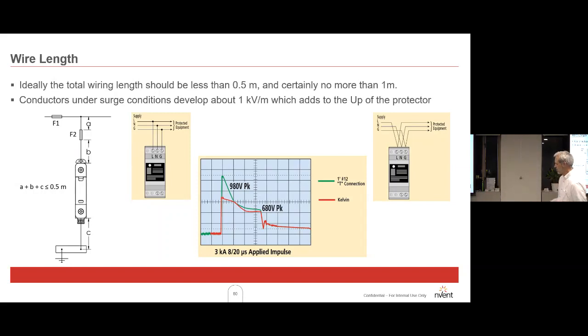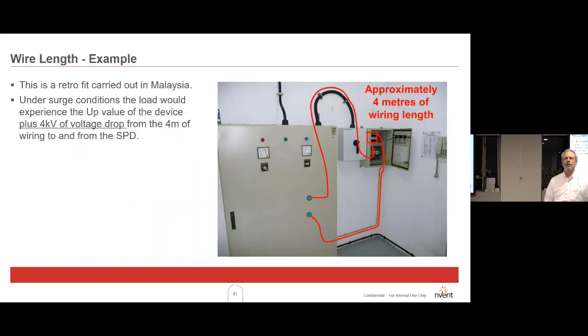I've had one situation I remember where I supplied these top performance surge diverters, and they came back to me a few months later and said our gear's been damaged by surges. It turns out the supply was in the top of the cabinet, and the cabinet was about 2 meters tall, and they put the surge diverter in the bottom. So they ended up with 4 meters of cabling. So that's 4,000 volts of less effectiveness of the surge diverter. If you're putting in a protection device, that can add to your length. So just be wary that you need to put that in a convenient location. That's an example of how not to do it, where they've retrofitted a surge protection device and got lots of cable length back to the switchboard.